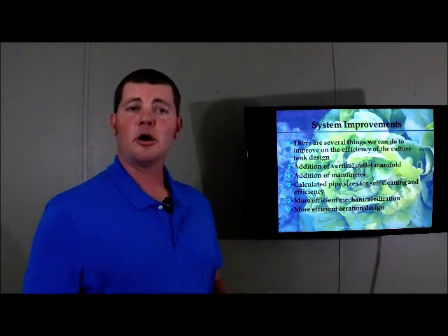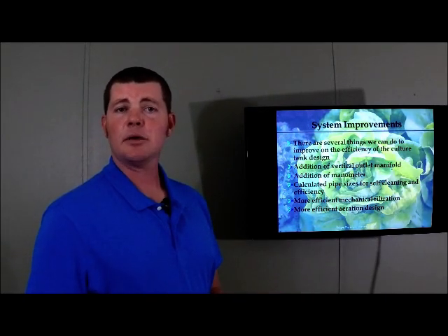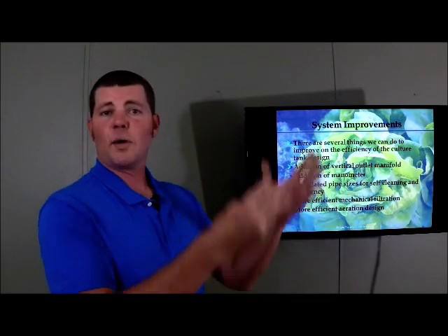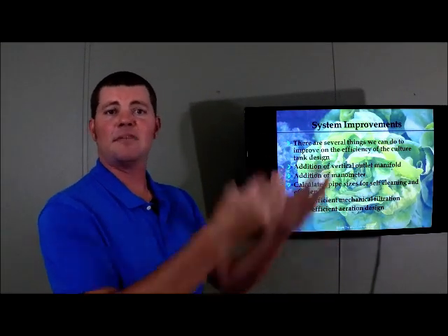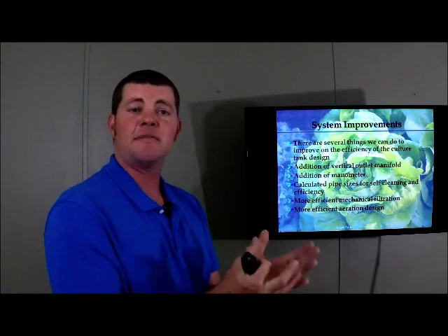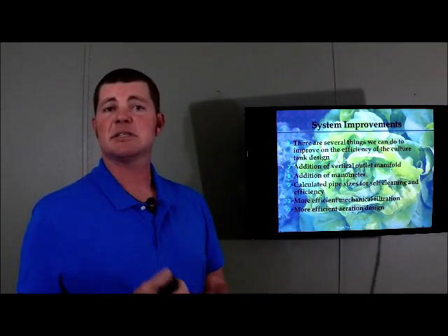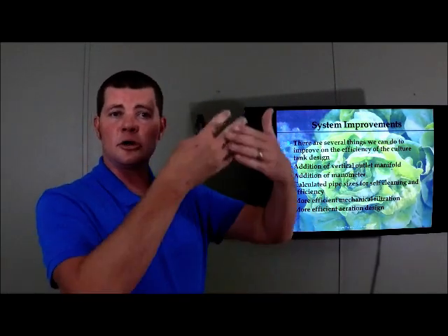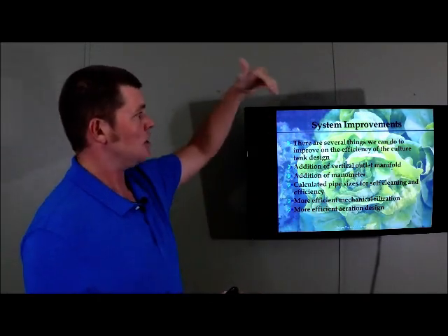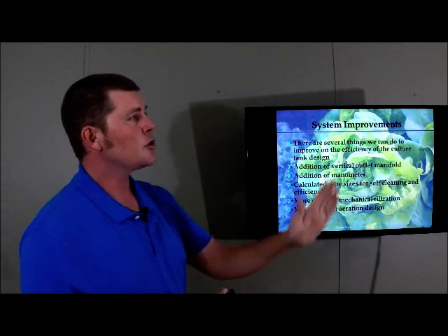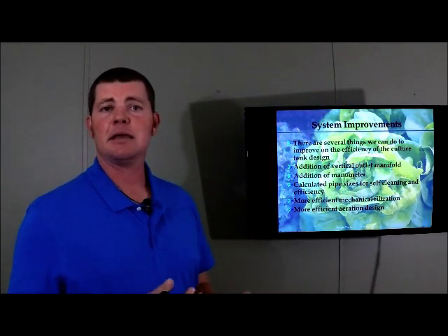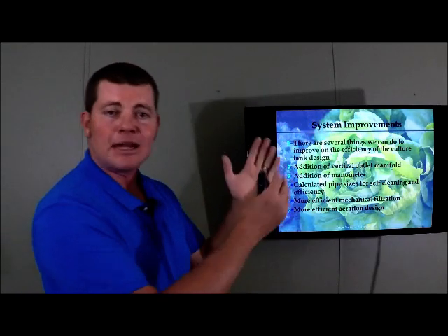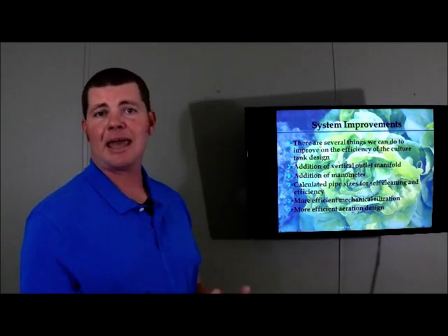It's basically a large cylindrical cone bottom tank with a 45-degree bottom with a hole. So the waste captures there. When we open a valve, it sucks the wastes out of the bottom of that cone and takes them to their stabilization pond. Well, in the middle of the filter is a large wall. So the water actually has to go down under the wall, travel back up, and then out of the tank.